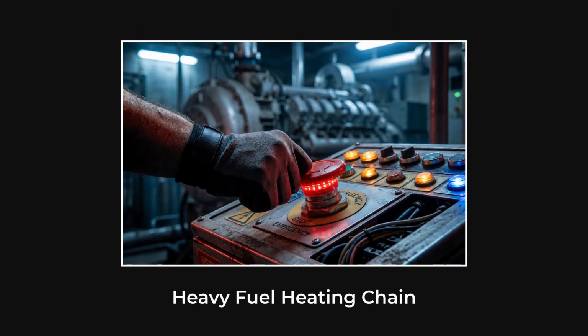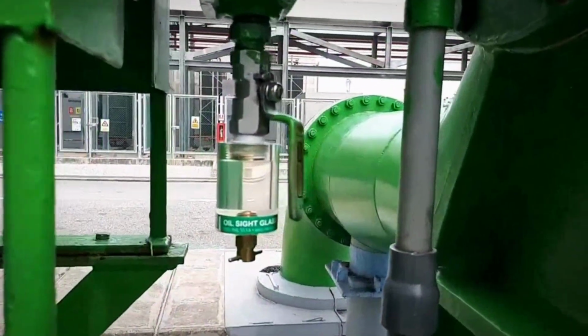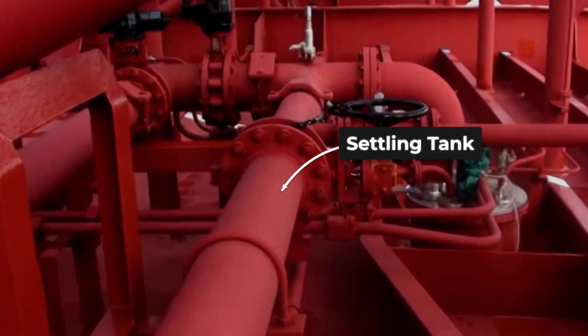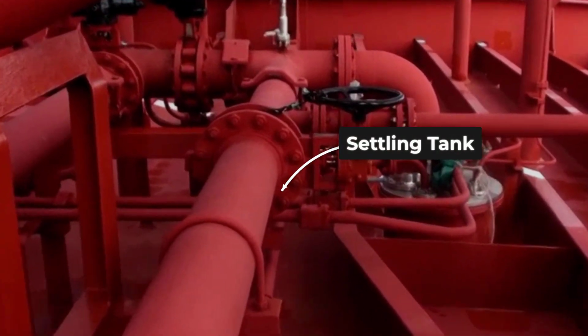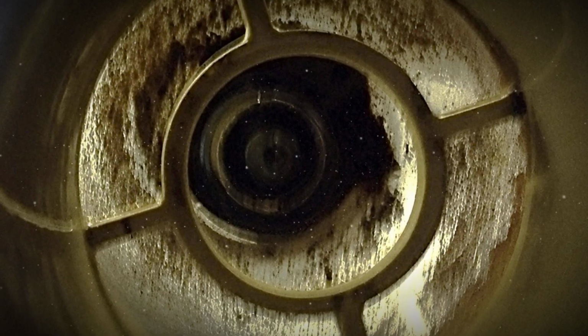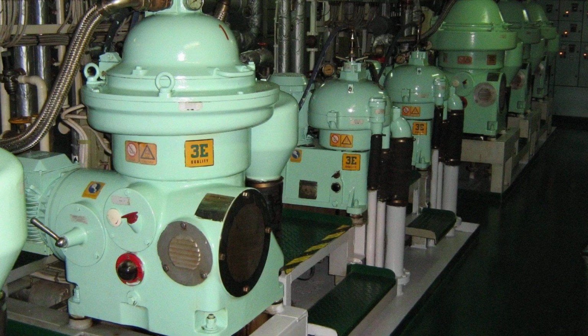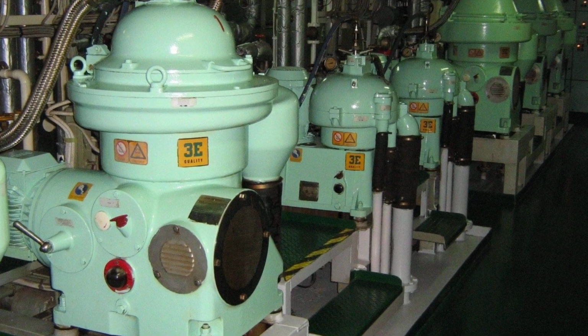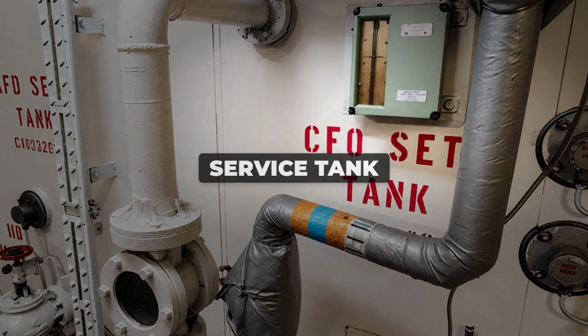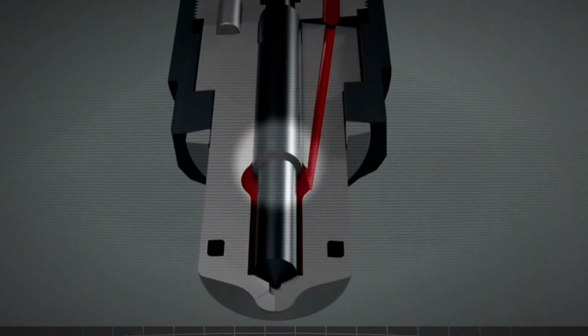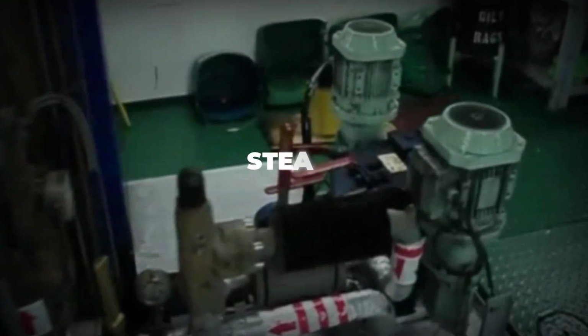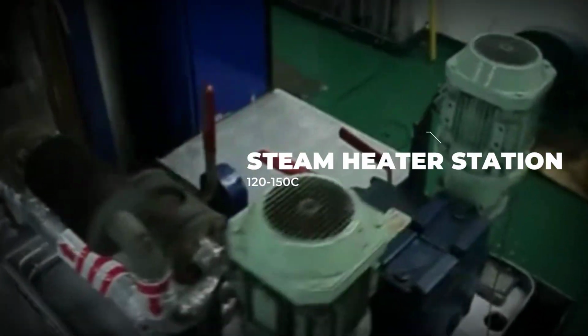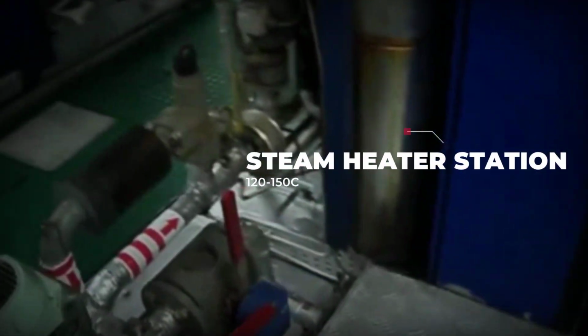The oil is maintained at 40 to 45 degrees Celsius in double-bottom storage tanks just to keep it fluid enough to move. It is then pumped into settling tanks heated to between 50 and 80 degrees Celsius, allowing water and heavy sediment to drop out. From there, the fuel passes through high-speed centrifugal purifiers before entering service tanks kept at up to 90 degrees Celsius. Finally, right before injection into the engine cylinders, steam heaters blast the fuel to between 120 and 150 degrees Celsius to achieve the fine mist needed for combustion.